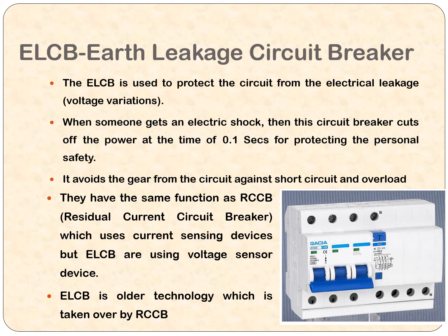If this equipment is delayed due to its architecture, naturally it fails. So ELCB is also a protecting circuit which senses earth leakage, that is, the voltage across the earth. If there is a voltage across the earth, there will be current flowing through it, and naturally that has to be detected and responded to. It needs some 0.1 seconds, that is 100 milliseconds, which is enough for the person to feel the shock. So that is a problem with the ELCB, but it protects the switchgear circuits against short circuit and overload. There is no doubt of it. But current based measuring devices are more preferable in this case, rather than ELCB.